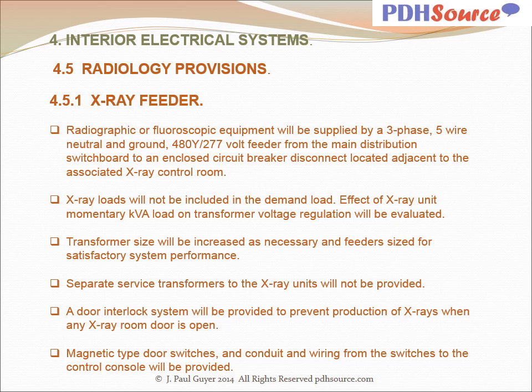With regard to provisions for radiology, X-ray feeder, radiographic or fluoroscopic equipment will be supplied by a three-phase, five-wire, neutral and ground 480Y-277 feeder from the main distribution switchboard to an enclosed circuit breaker disconnect located adjacent to the associated X-ray control room. X-ray loads will not be included in the demand load. Effect of X-ray unit momentary KVA load on transformer voltage regulation will be evaluated. Transformer size will be increased as necessary and feeder sized for satisfactory system performance. Separate service transformers to the X-ray units will not be provided.